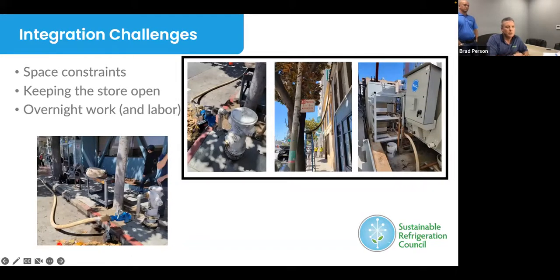So this one, we're going to start with the picture all the way to the right. In this design for this location, which was the transcritical CO2, we had an approach because they had a closed loop water system existing that ran the refrigeration. As we were looking at using that structure, we had to play some musical chairs, I call it. But we didn't have a way to get the new transcritical rack operating and enough space for its corresponding adiabatic gas cooler. So Hill Phoenix put together a skid for us with the heat exchangers, and we used the existing loop to pipe water to those heat exchangers and use them as the gas cooler interim until we could get the supports available for the framework.